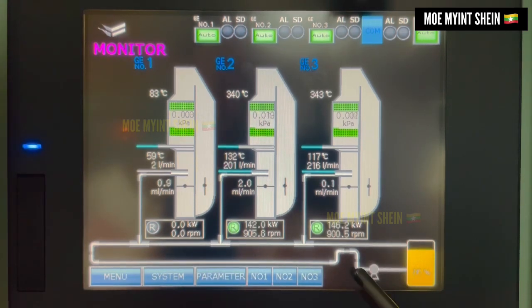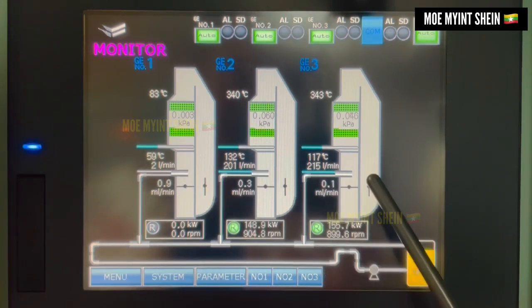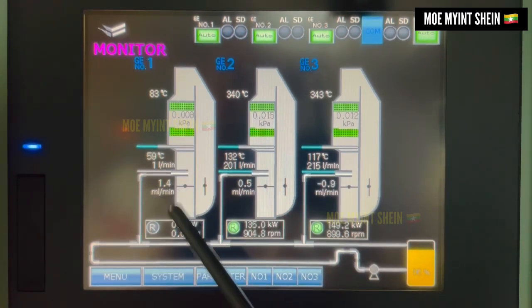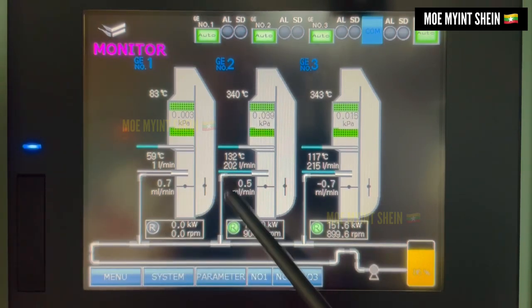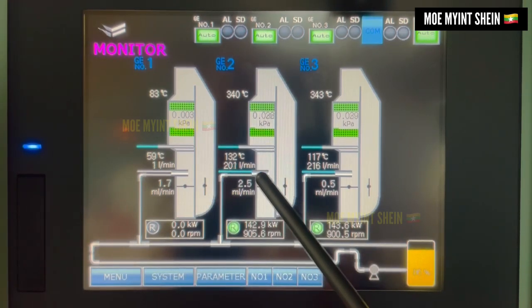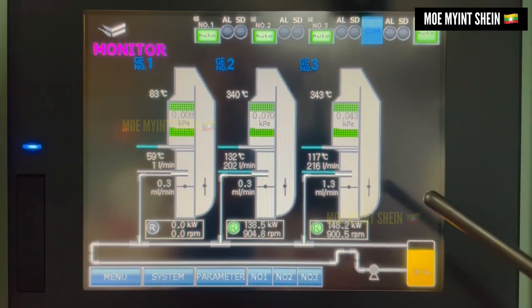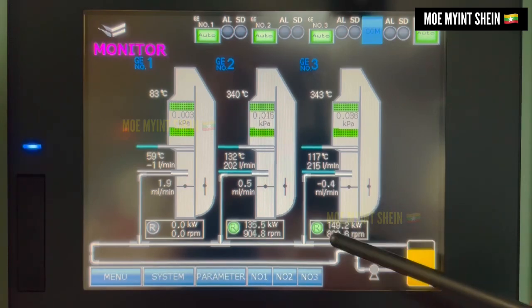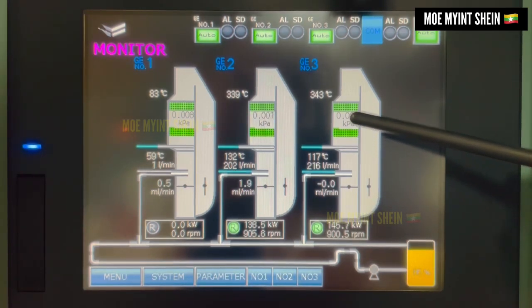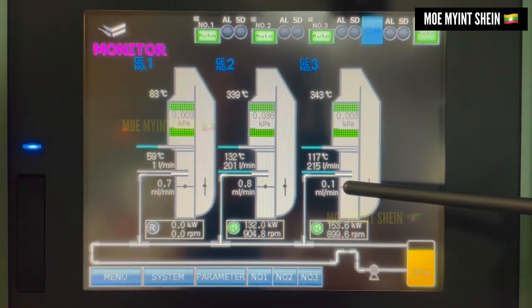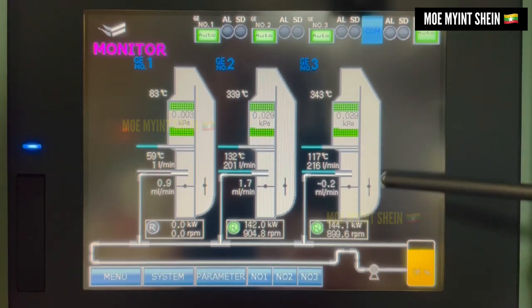The urea pump takes suction from the urea tank and supplies urea to the injection nozzles. During SCR system operation, the urea pump automatically starts and supplies the required amount of urea to the injection nozzles for running generators. Urea water is injected into the exhaust stream with the assistance of compressed air. The system is not in use at present — that's why the damper to the catalytic chamber is closed and the bypass damper is in open position.